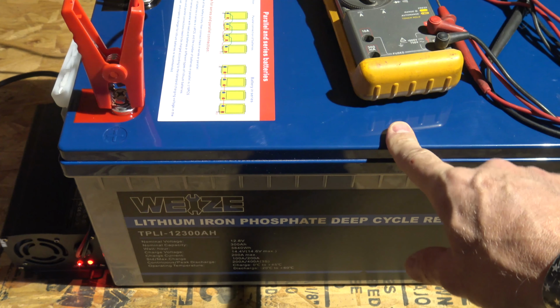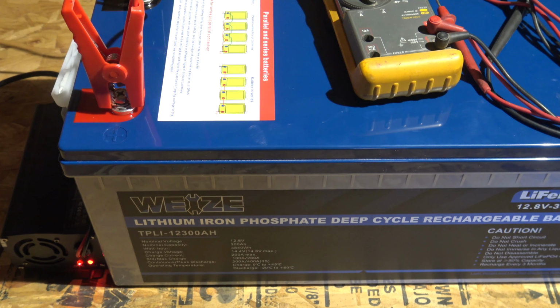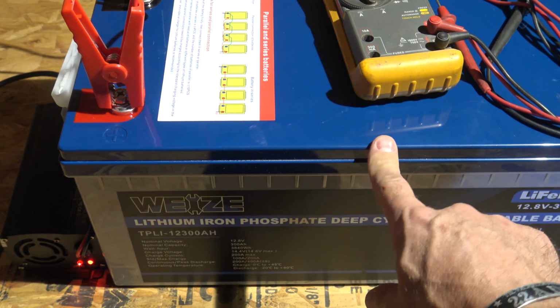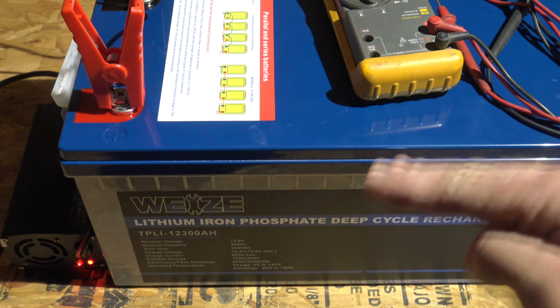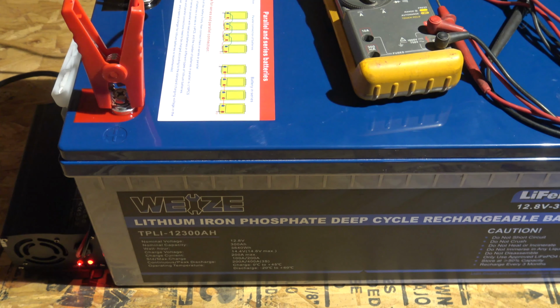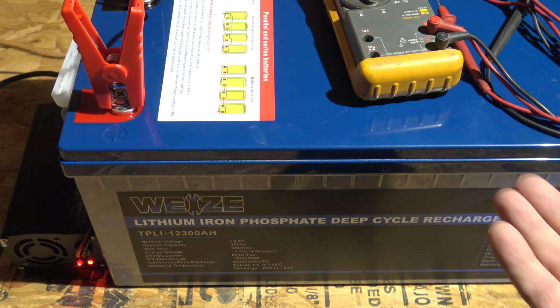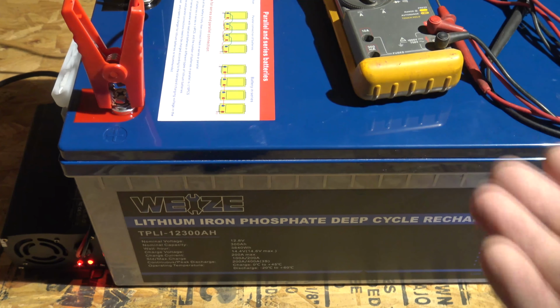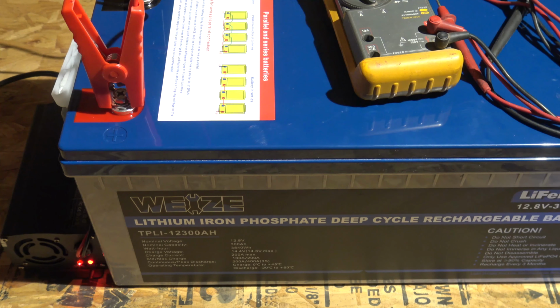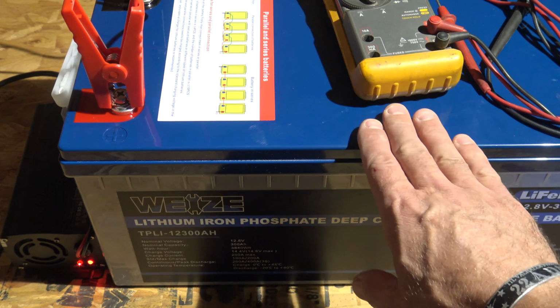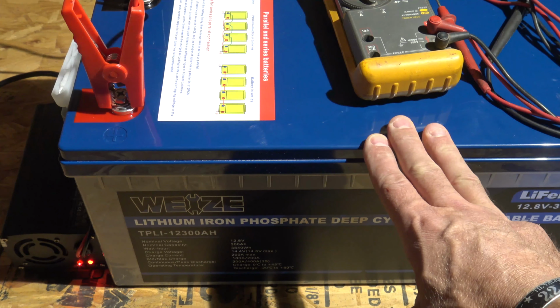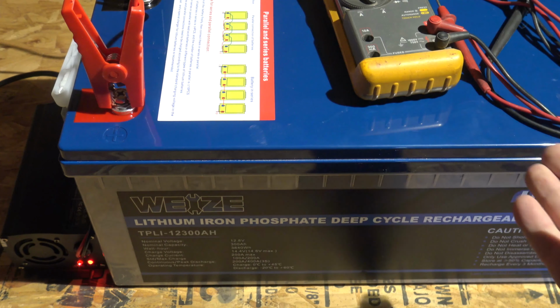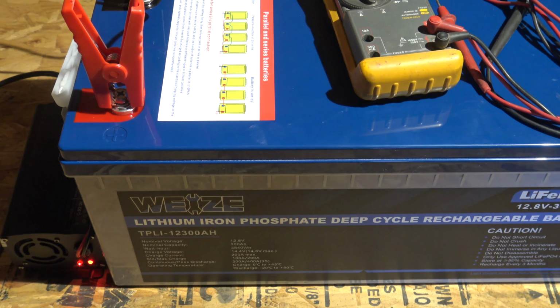That's absolutely fantastic, and in fact that's what they suggest for how you run this battery. They don't want you to drop it below 50%. It won't hurt it if you do, but if you keep it above 50%, you're going to get a tremendously longer runtime. So 8,000 cycles at 365 days a year is over 20 years, folks. That's a long, long time.